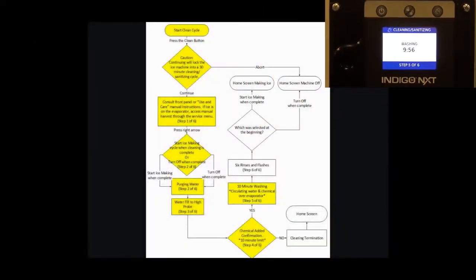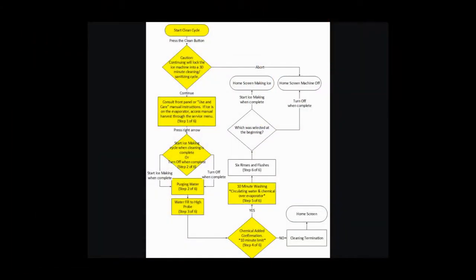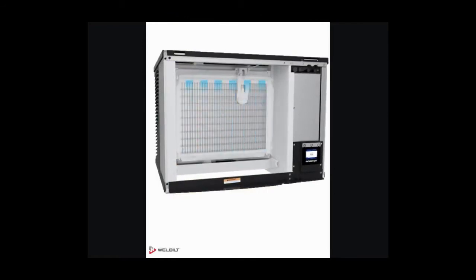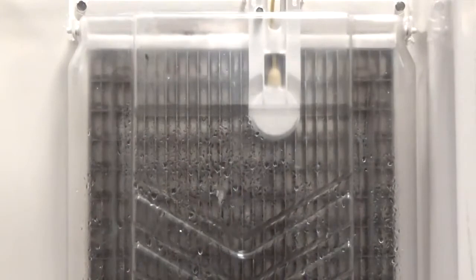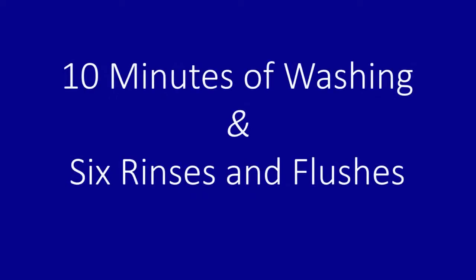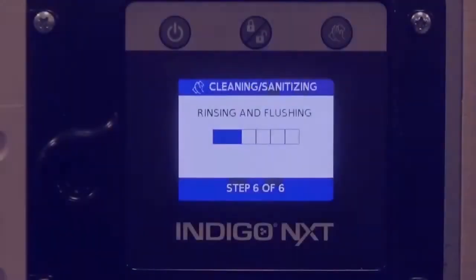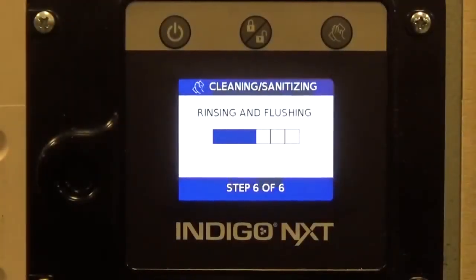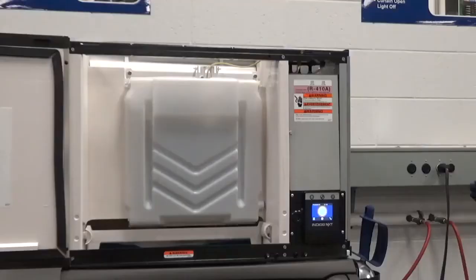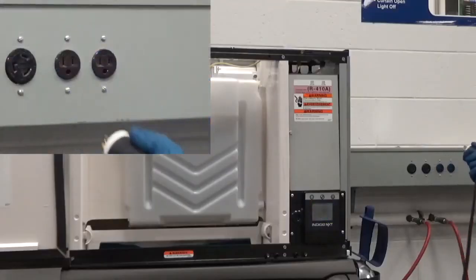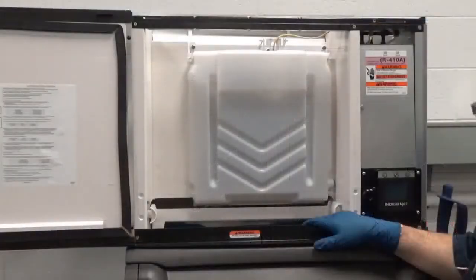Step 4. Wait until the clean cycle is complete, approximately 24 minutes. This depends on the incoming water pressure, which affects the length of the rinse and flush cycles. The clean cycle comprises 10 minutes of washing, followed by 6 rinses and flushes. After complete, disconnect power to the ice machine and dispenser when used.